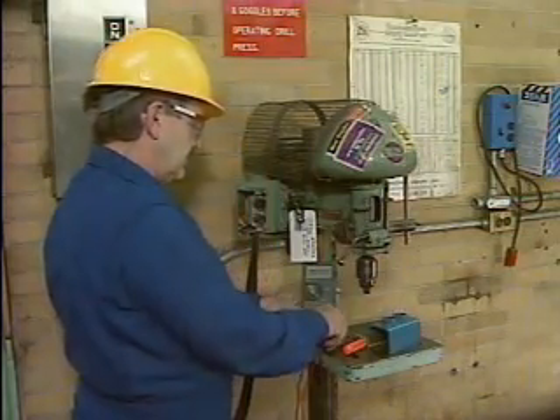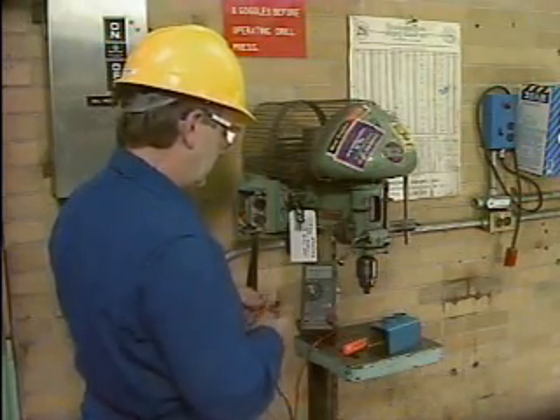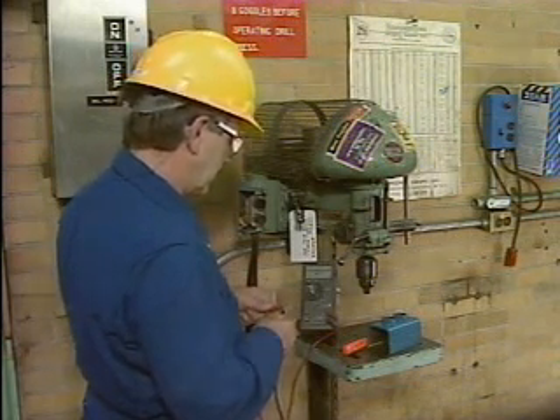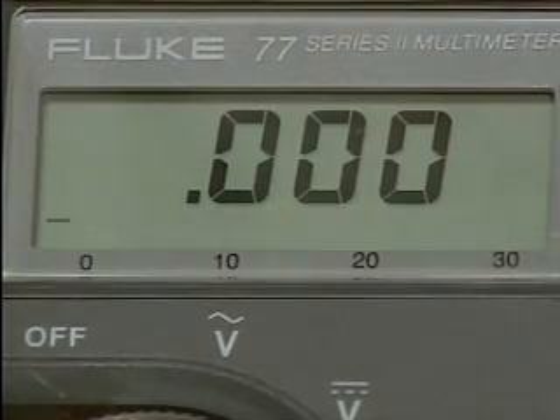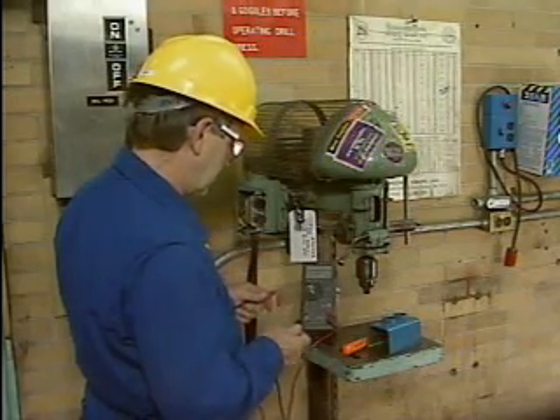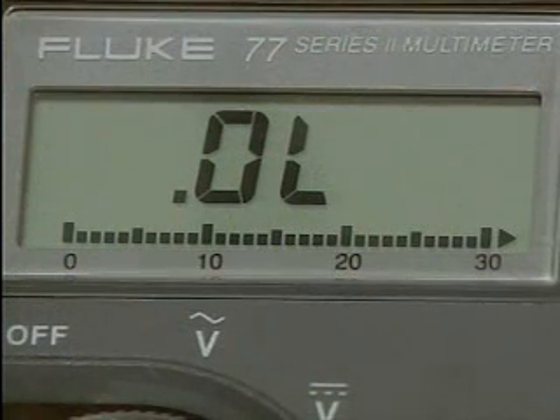After setting up his multimeter to check continuity, he holds the test probes together. The display and the audible tone tell the electrician that the instrument can indicate a closed circuit path. Then he holds the test probes apart. The display's indication and the lack of an audible tone from the multimeter tell the electrician that the multimeter can indicate an open circuit path.